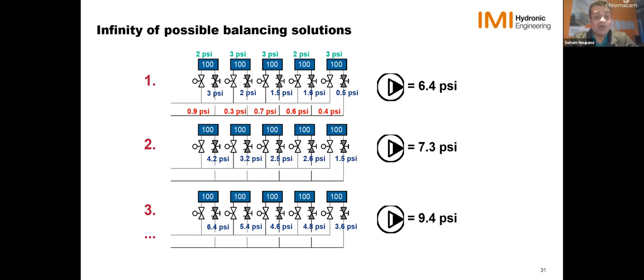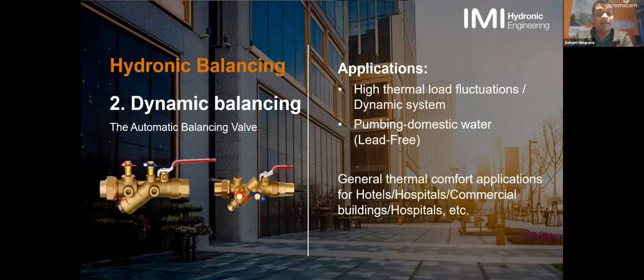And with that, I'm going to go to our second solution, which is dynamic balancing, also called automatic balancing. This is good for high thermal load fluctuations and for any kind of general thermal comfort application, of course. Let's look at how this is different from manual balancing, which we just looked into in so much detail.